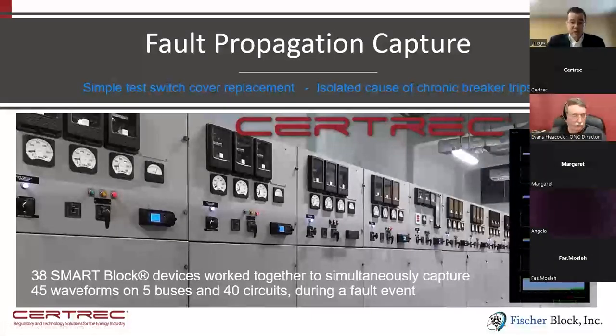And here's an example where we did an implementation at a substation on the grid, whereby we installed approximately 40 sensors, I think 38 smart blocks, as it says there, all doing continuous monitoring of the voltage and current, three-phase volts and current signals going out to the grid. They're all communicating with each other through the local network in the substation, such that if any one device triggers on an event of interest, it sends out a trigger signal to all the others. And so they all capture their respective three-phase volts and current bus and feeder circuits at the same time.